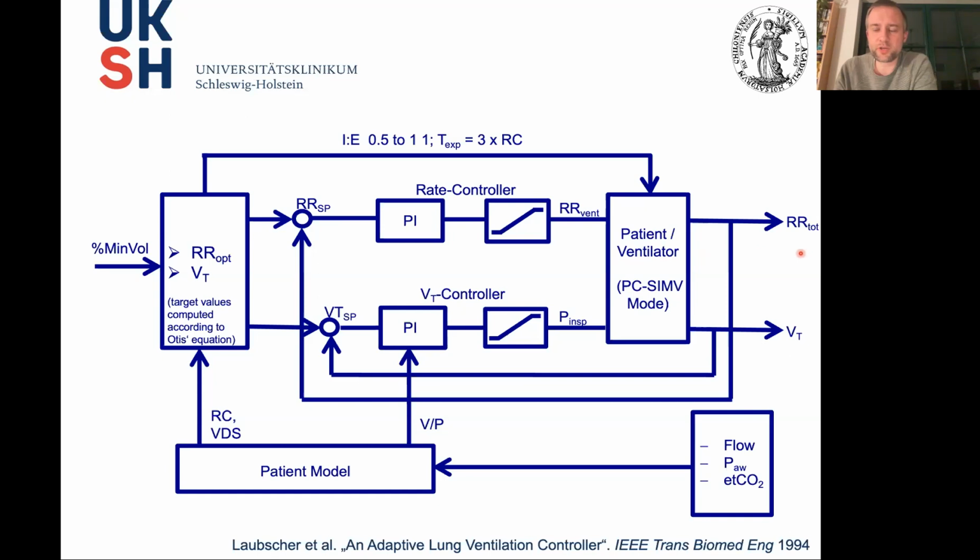And then it's important to understand what's the result. And the result is always some combination of respiratory rate and tidal volume that will result in this minute ventilation that we entered as users. So this is how such a controller works.